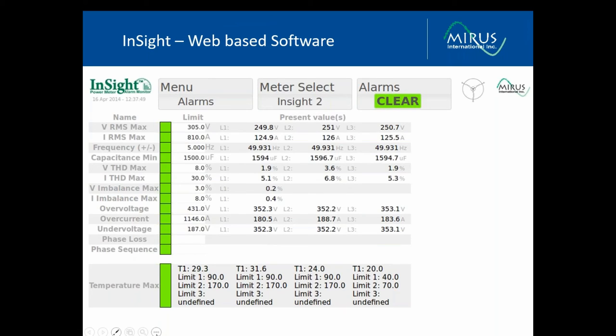Various alarms that we can set are shown here, with voltage RMS max and current RMS max values, frequency variations, capacitance of the filter, so making sure that it's still near our design capacitance, the voltage and current distortion, voltage imbalance, and so on. And we also monitor various points within the filter on the reactor for temperature levels, and can provide early condition-based monitoring of the filter itself.